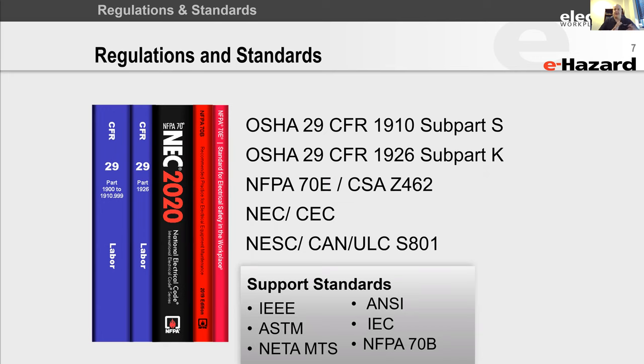Or there's the other option that 70E and OSHA give us, the idea that de-energization would create some sort of additional hazard or increased risk. That's creating a situation where it is more dangerous to turn the power off than to simply leave it on. But the number of times that happens these days is much, much more fewer and far between.